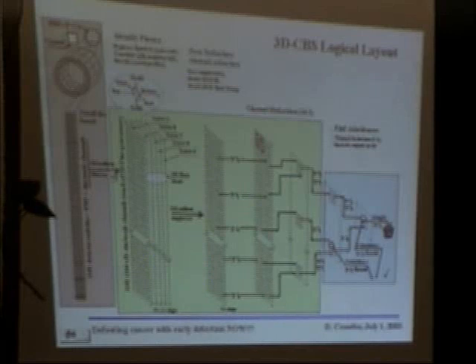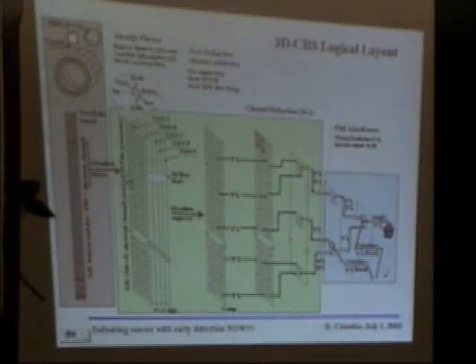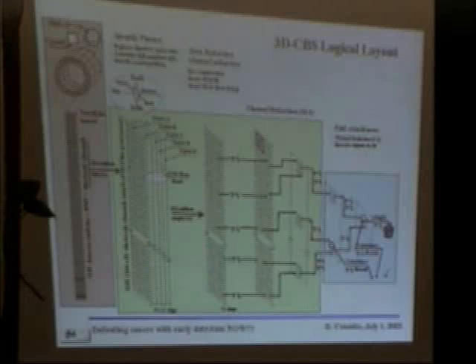However, because you would like to capture all the photons, not lose any of them, then the first one, we go to the first processor, and then, while this processor is busy, the second event, we go to the second layer of processor. I call it an array, a completely independent array of processor, and so on, until you put as many layers as the complexity of your algorithm. Those two parameters are the ones that determine the number of layers. And that will guarantee there will be that dead time-free electronics.